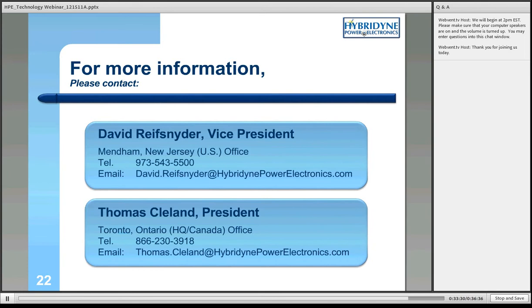I think what the questioner is referring to, we call a booster box approach from SatCon, and it's also a Canadian manufacturer, as we are. They're one of the few companies that does offer a lower threshold input voltage. I can't say specifically that I'm familiar with it being at 50. I'll take that at face value. We understand that if you look at the components required to configure the booster box configuration, it creates a very expensive solution from SatCon. So we have found it to be something where we're still competitive with a SatCon solution, but we would agree that it's one of the only ones that we're aware of in the marketplace that has a distributed, albeit not in the inverter, approach to providing a lower input voltage, higher yield inverter.